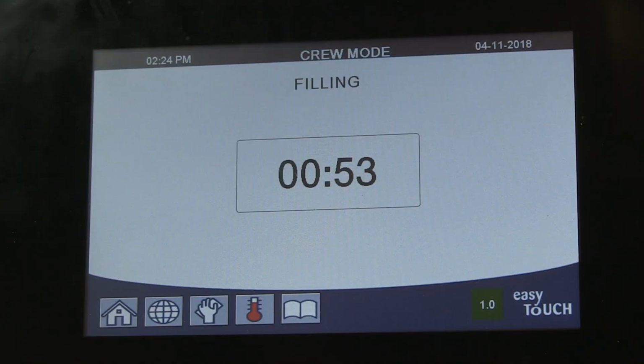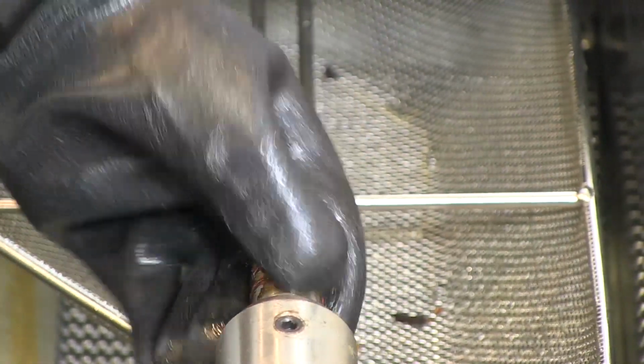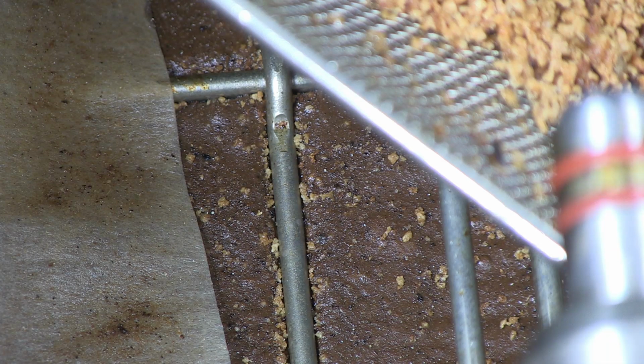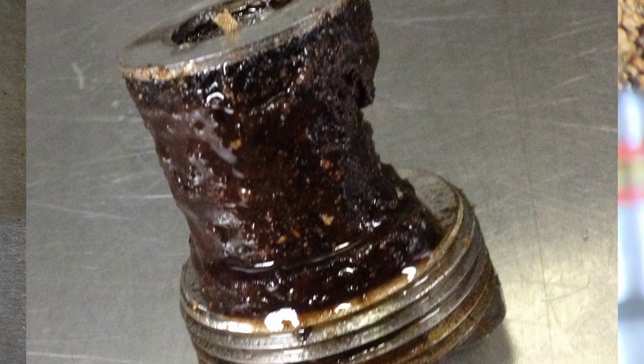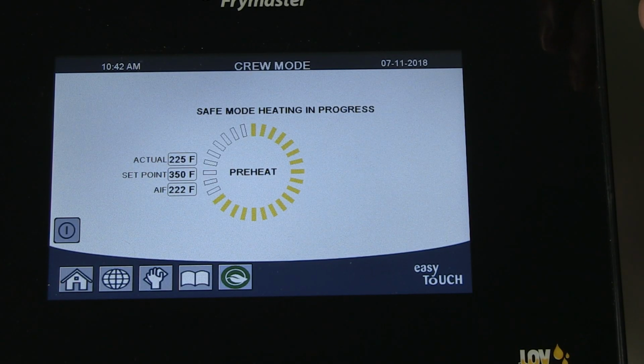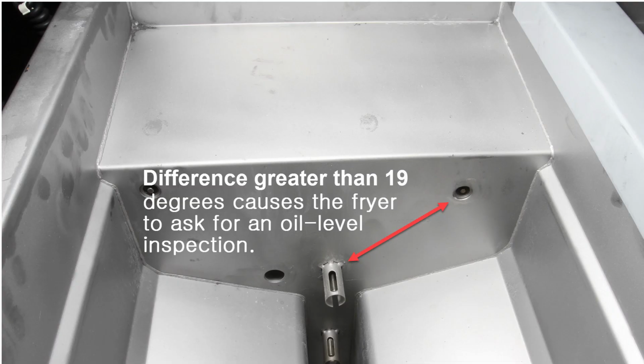to full burn. The problem is usually caused by oil failing to return to the fry pot after a filter cycle. The cause can be bad O-rings on the filter pan pickup, dirty filter pan, or a clogged inline filter. The fryer's efforts to rectify this can take several minutes, and there'll be times when the controller is displaying heating in progress, although it's not calling for heat. The burners are only active when the heat icons are on the display.